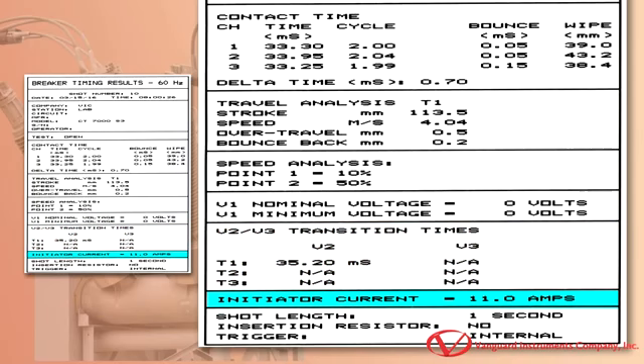The measured open coil current is shown here. For this example, the initiate current was 11 amps. This last section shows additional test information. We can see that the shot duration was 1 second, there was no insertion resistor in the circuit breaker under test, and the trigger mode was set for internal trigger.